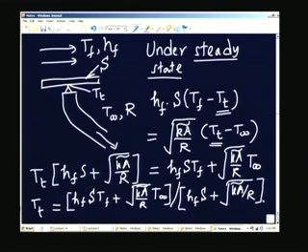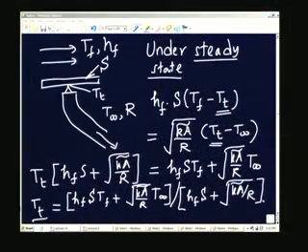This expression indicates that the temperature indicated by the thermocouple, that is the left hand side, this is what is measured, is a weighted mean of the temperature Tf, the weighting factor being Hf into S. So, this is the weighted mean of Tf multiplied by the weight factor Hfs plus the weighted mean of T infinity with the factor square root of Ka by R. That means, I am not going to get either Tf or T infinity, depending on of course the particular case.